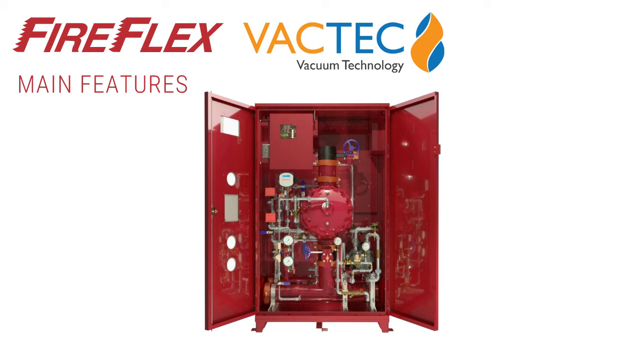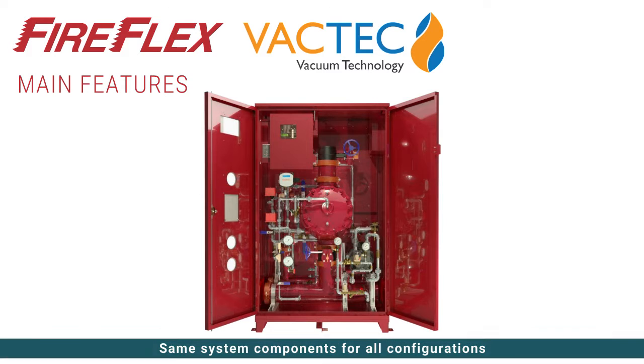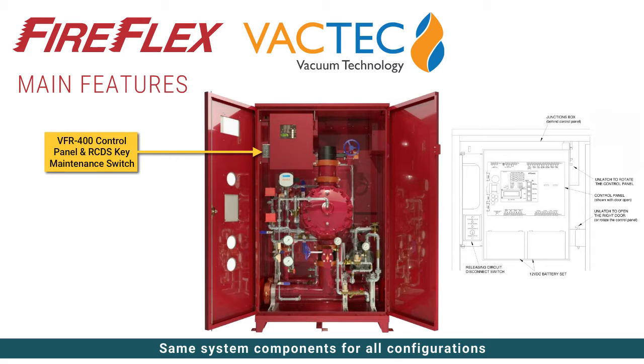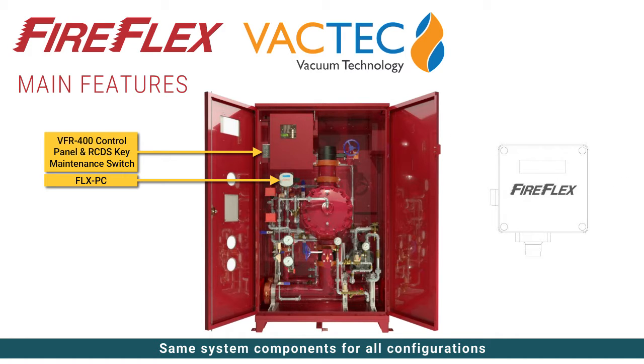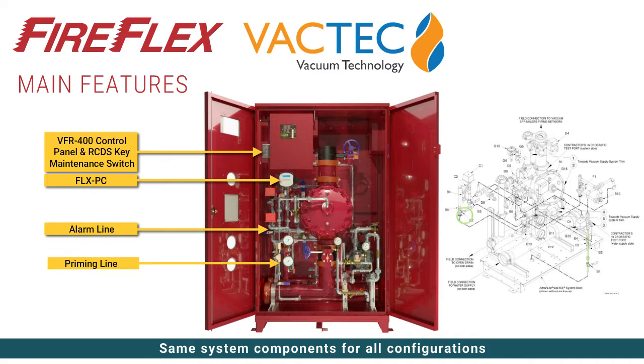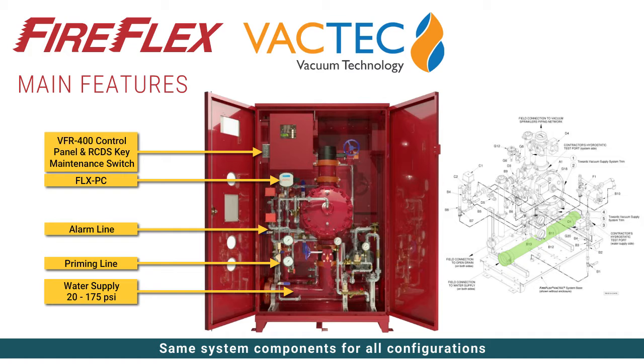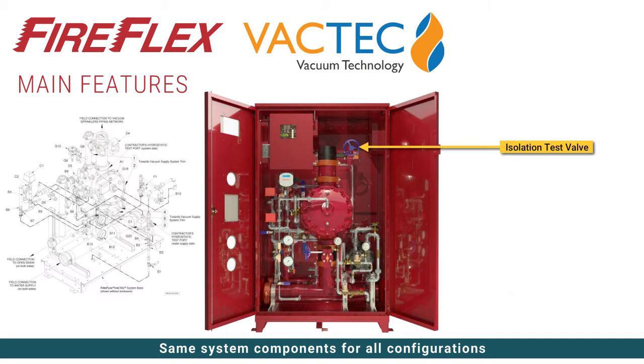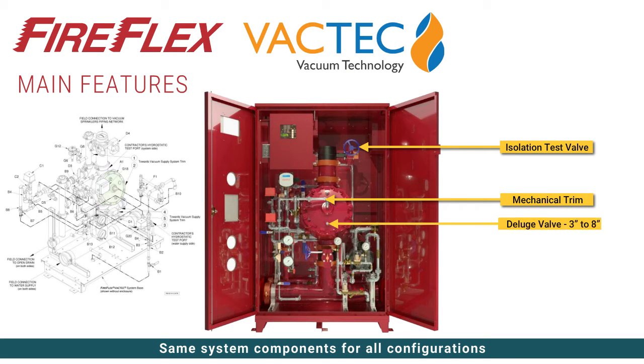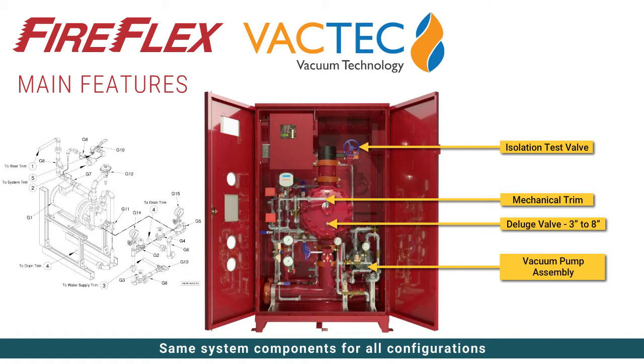Here are the main features of the Vactec. All configurations use the same system components: VFR 400 control panel and RCDS key maintenance switch, FLX PC, alarm line, priming line, water supply from 20 to 175 psi, isolation test valve, mechanical trim, deluge valve 3 inches to 8 inches, and vacuum pump assembly.